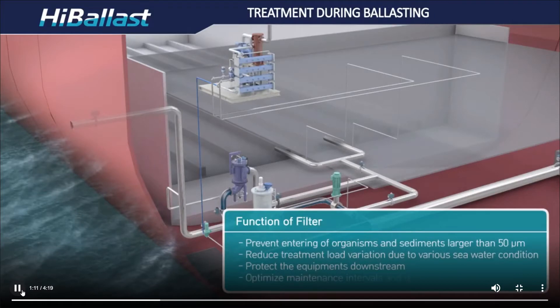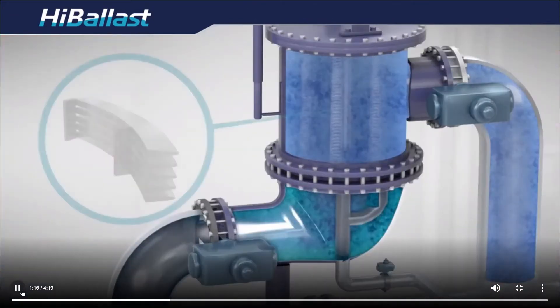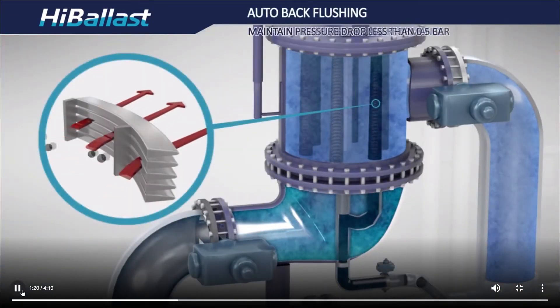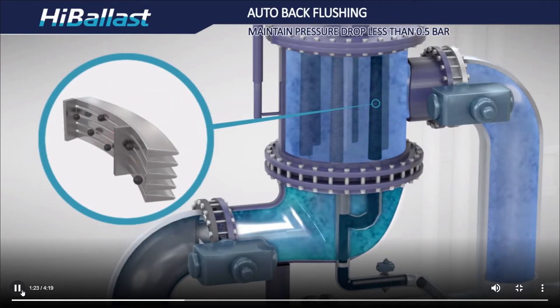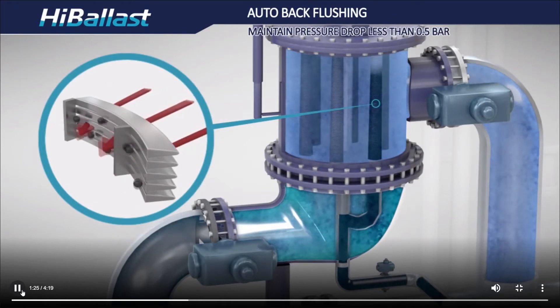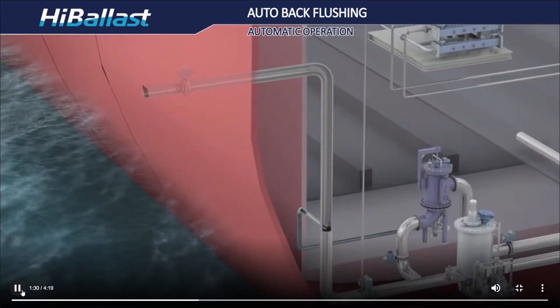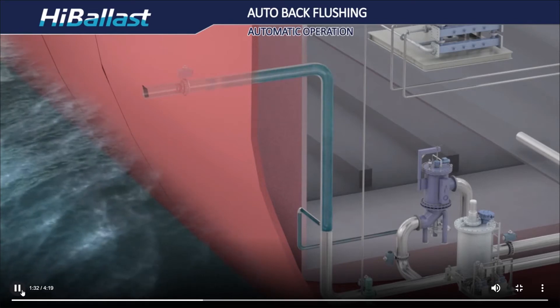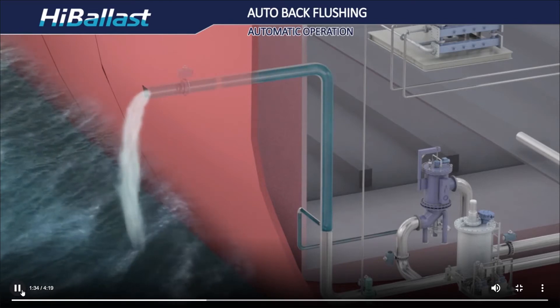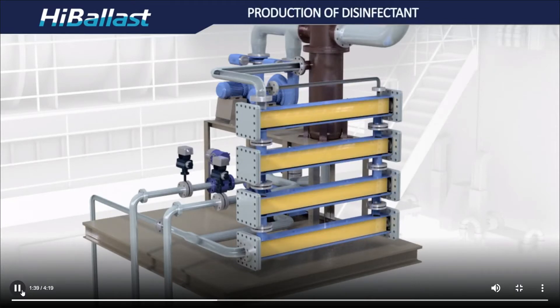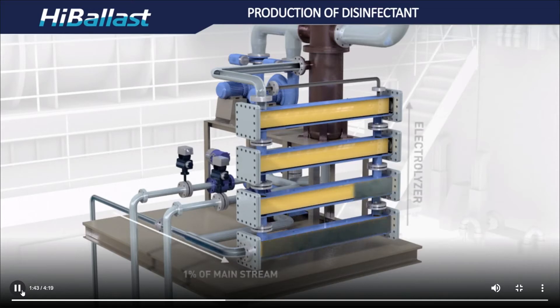To perform robust BWTS performance, in case the differential pressure between filter inlet and outlet increases up to 0.5 bar due to foreign substances getting stuck, back-flushing starts automatically to wash the foreign substance out, resulting in minimum filter maintenance.